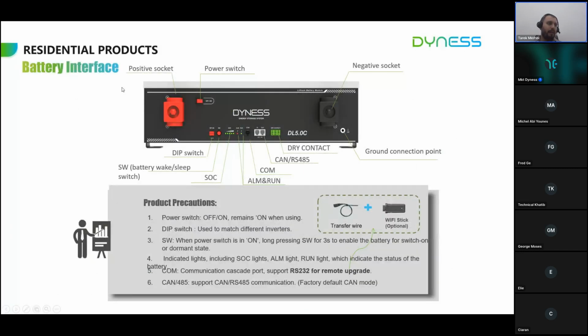On the battery interface, we have the DIP switch to be configured according to the brand of inverter. For example, a Solis inverter should be configured 0010, according to the brand of inverter and application case. This switch is for battery wake or sleep, the SOC level, alarm com, and here we have the CAN communication or RS485 communication according to the brand of inverter. And as we said before, we have the optional Wi-Fi stick to access the battery or the stack. Also, we can use this Wi-Fi stick for remote upgrade if needed.